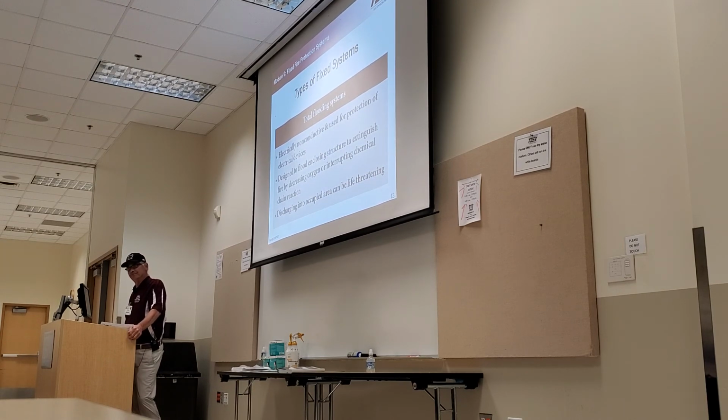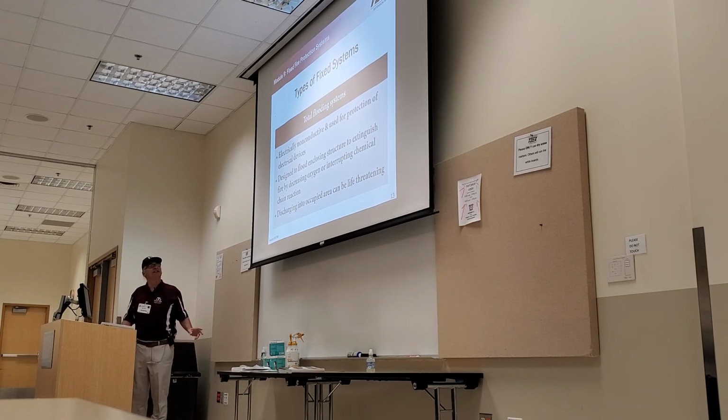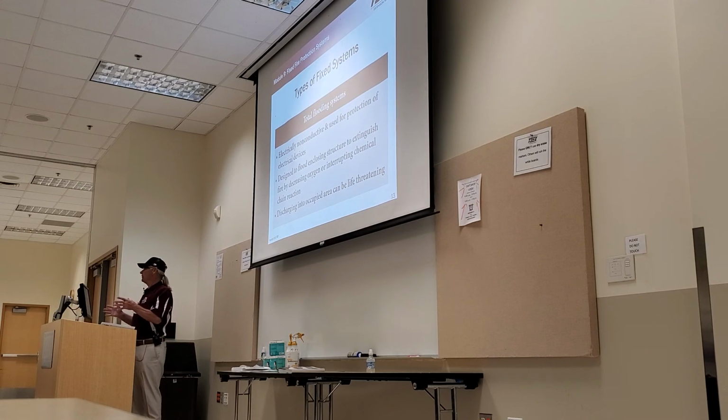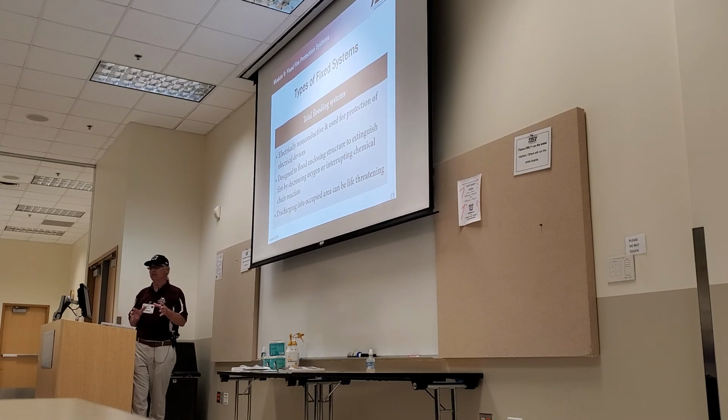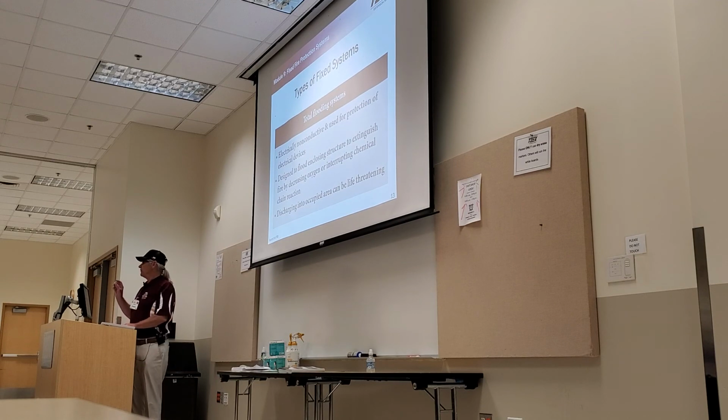Carbon dioxide. We breathe the same amount of oxygen that fire needs. You don't go into a contained space with less than 19% oxygen. That's when the flame starts flickering. You start getting dizzy. When it gets down to 16%, the fire goes out, and so do you.